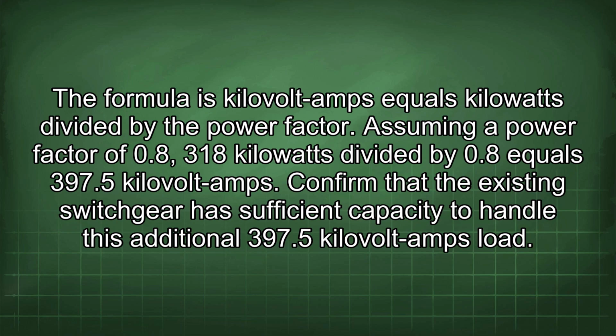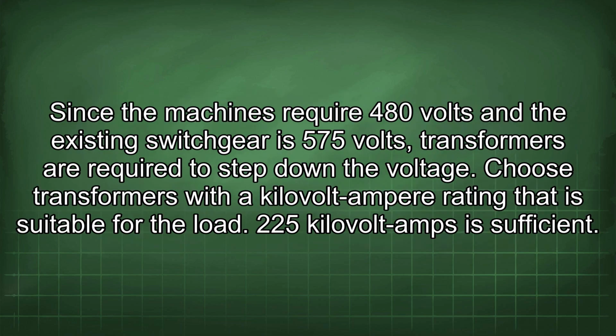Confirm that the existing switchgear has sufficient capacity to handle this additional 397.5 kilovolt amps load. Since the machines require 480 volts and the existing switchgear is 575 volts, transformers are required to step down the voltage. Choose transformers with a kilovolt ampere rating that is suitable for the load. 225 kilovolt amps is sufficient.